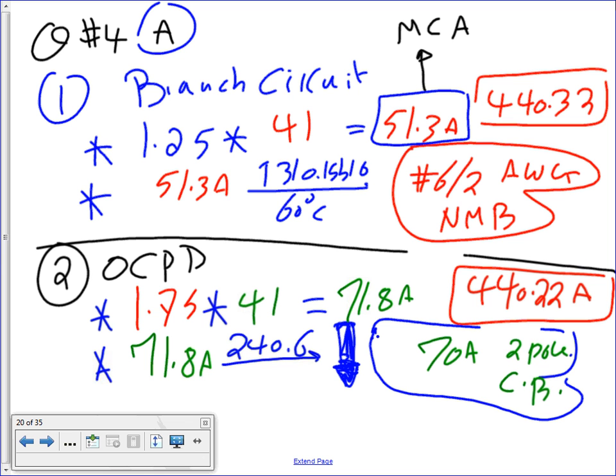Any comments, guys? Any questions? Why did I go down? If you read 440.22, it doesn't tell you to go up. So if you can't go up, you can't stay where you are. What are you going to do? Think about it. You can't go up because you're not allowed to. You can't stay where you are because they don't make the size that you're looking for. So your only option is what? Going down. So you go down to 70 amps.